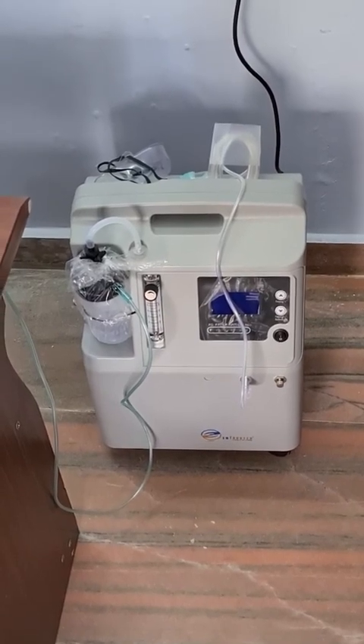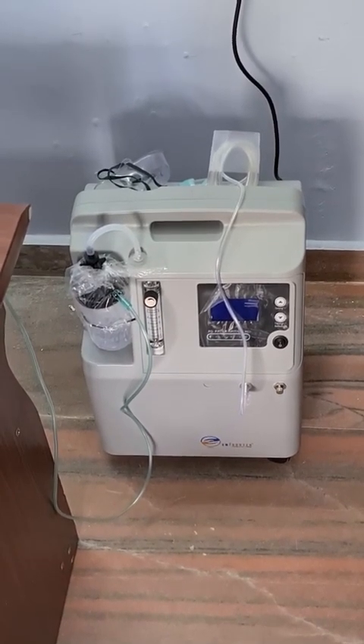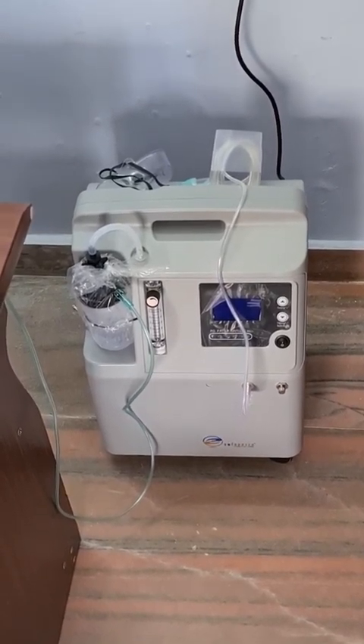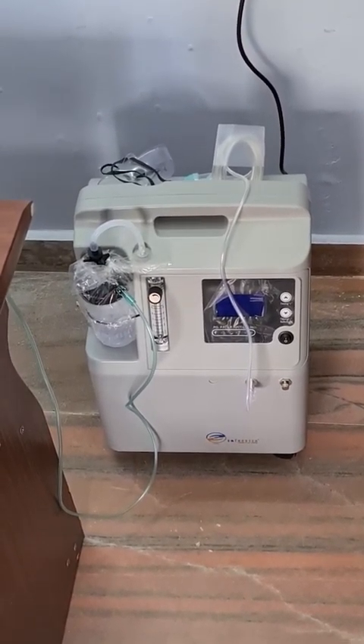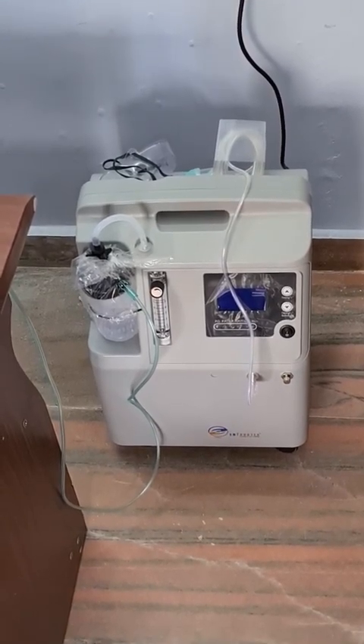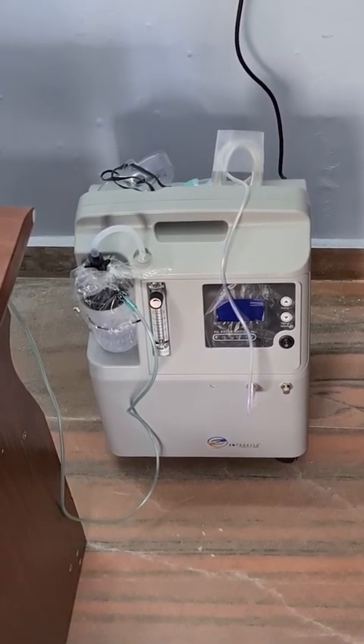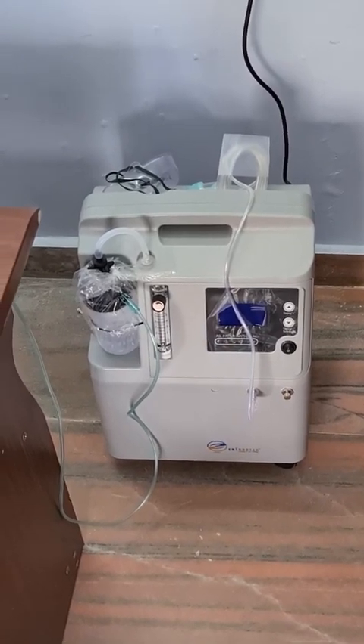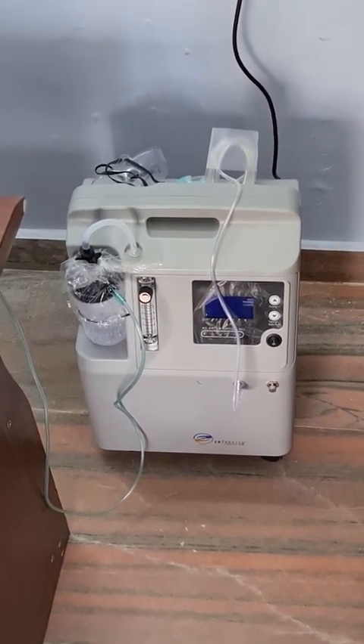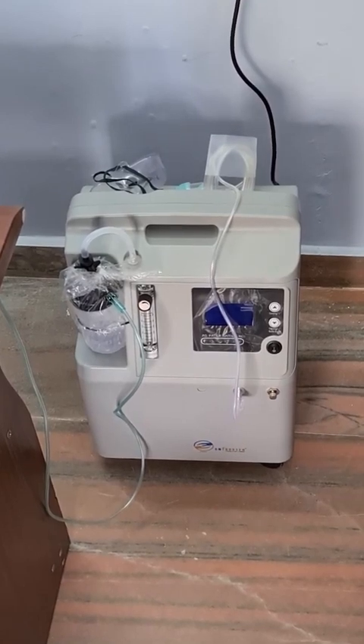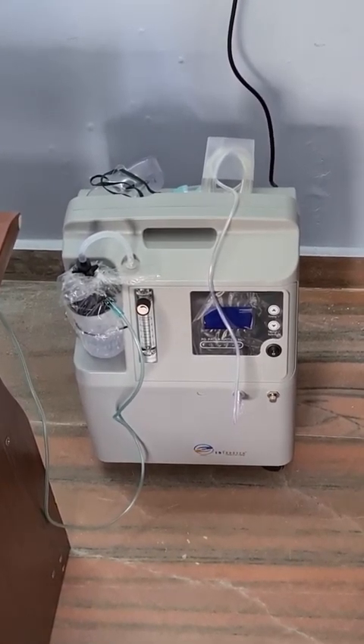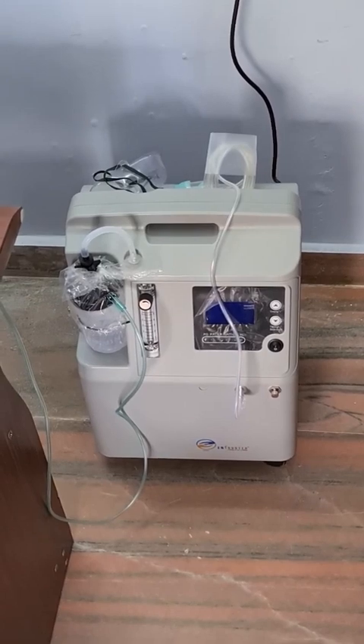It is not that you cannot run it. You can very well run the machine for even more than 48 hours. Even the alarm settings indicate that you can keep it at 48 hours for one complete stretch. But the correct procedure to reduce the load on the compressor is to give the machine a break once every 8 hours. Then the lifetime of the compressor, the filters and the overall equipment will be longer. So that is a kind recommendation.